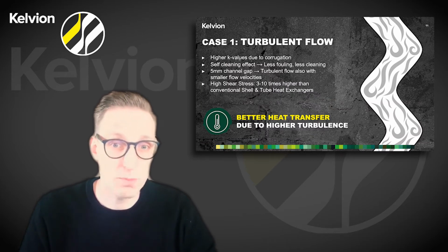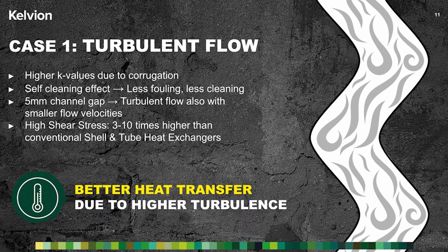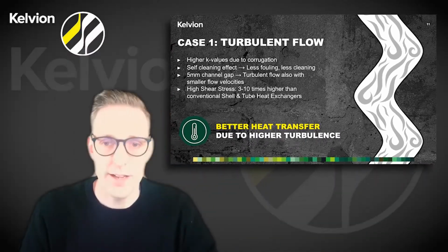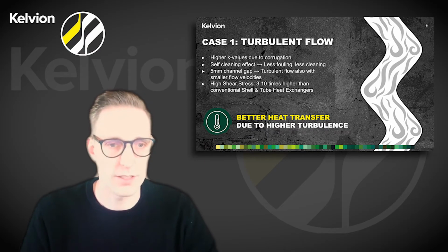The heat transfer takes place in the gap between two heat transfer plates. Here we can find, due to the geometry, a high turbulence which promotes proper and good heat transfer, meaning it results in higher heat transfer coefficients, or so-called K values. The turbulent flow also creates a self-cleaning effect and reduces the fouling tendency, which leads in the end to longer service intervals of the heat exchanger. This can be expressed with the so-called shear stress, which is 3 to 10 times higher than in conventional shell and tube heat exchangers.